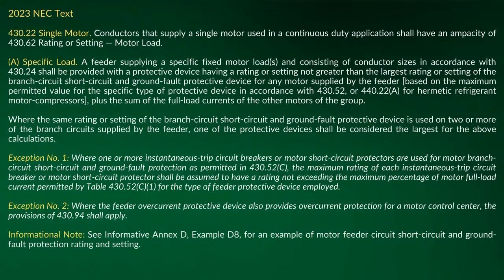A feeder supplying a fixed motor load or loads consisting of conductor sizes in accordance with which section? 430.24. And then if you go down to the second paragraph, it says, where the same rating or setting of the branch circuit short circuit and ground fault protective device is used on two or more motors on the branch circuit supplied by what? The feeder. See? That tells me right there you've got two or more, so that pertains to several motors. That's what a feeder goes to, not a branch circuit. A branch circuit goes to an individual. So if I'm going to an individual motor, how can that be a feeder at that one disconnect?